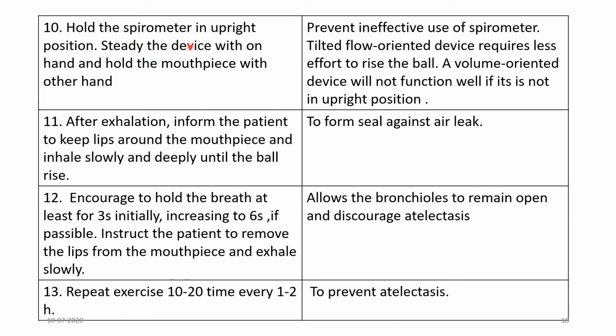Hold the spirometer in an upright position. Steady the device with one hand and hold the mouthpiece with the other hand. That prevents ineffective use of the spirometer. If the spirometer is in a tilted condition, the ball will rise with less effort, and the volume-oriented device will not function well if the device is tilted.